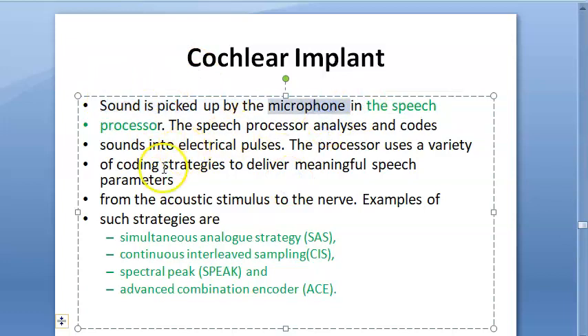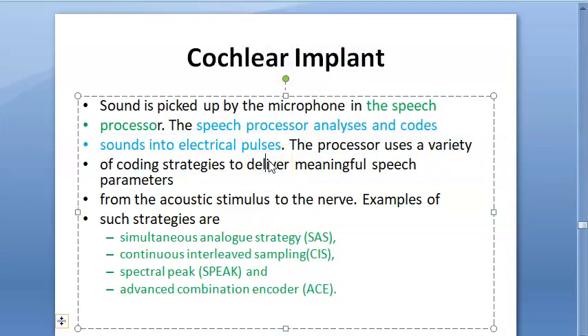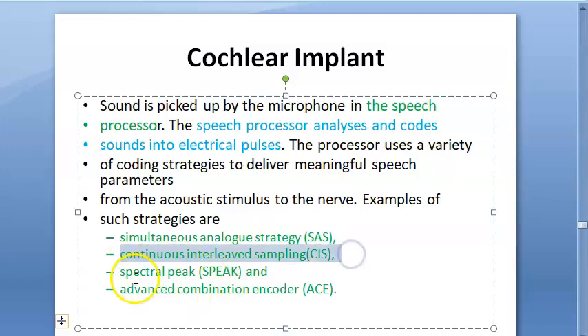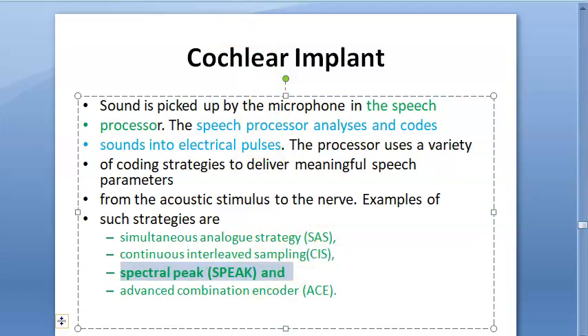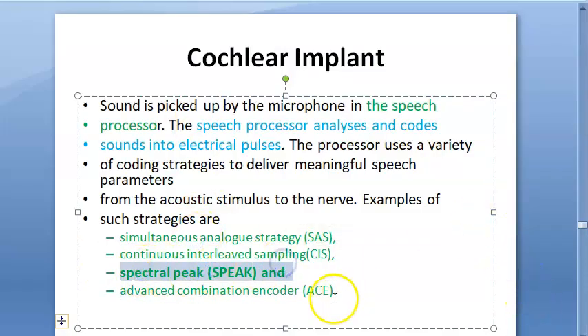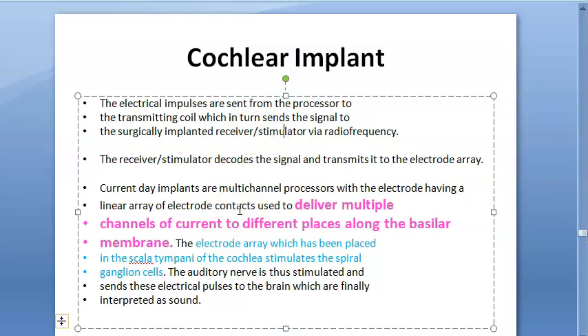Sound is picked up by the microphone in the sound processor. The speech processor analyzes and codes sound into electrical pulses. There are various coding strategies to deliver meaningful speech parameters: simultaneous analog strategy, continuous interleaved sampling, spectral peak - SPEAK. The spectral peak SPEAK strategy is one to remember. Also there is advanced combination encoder - ACE. The SPEAK strategy converts sound into electrical signal.